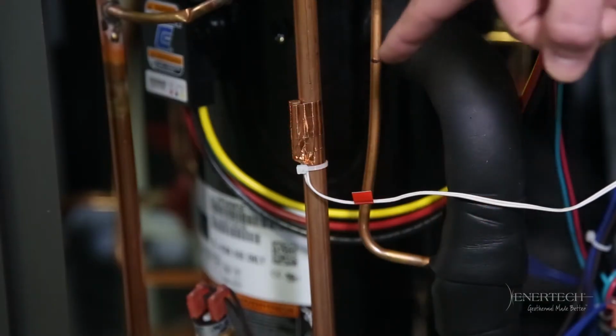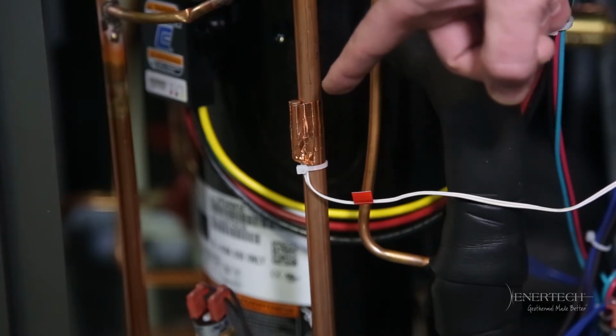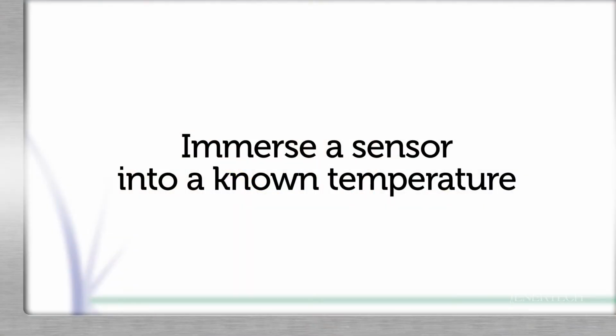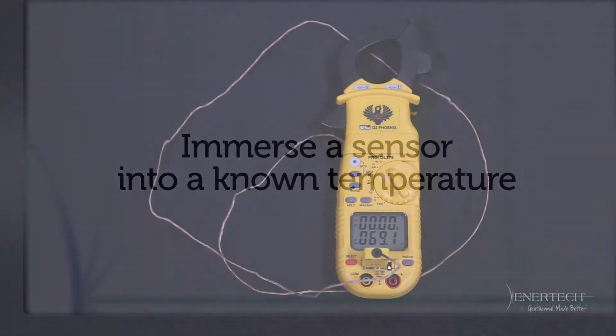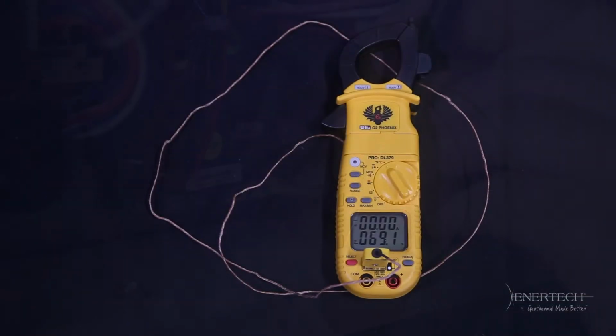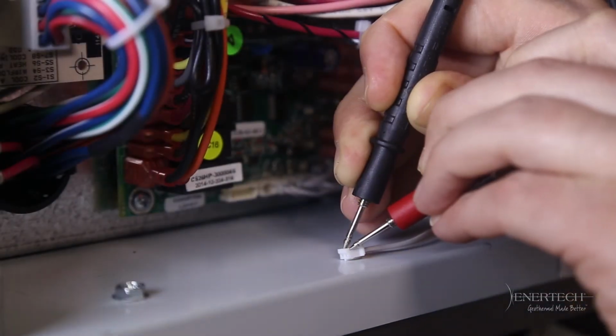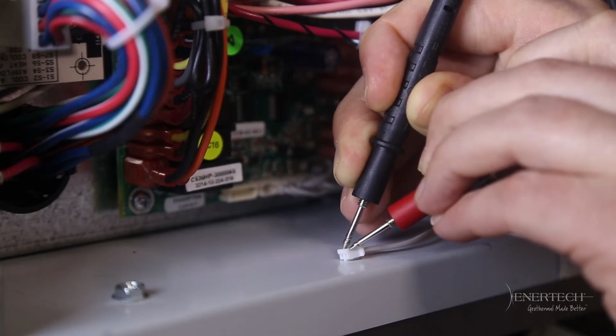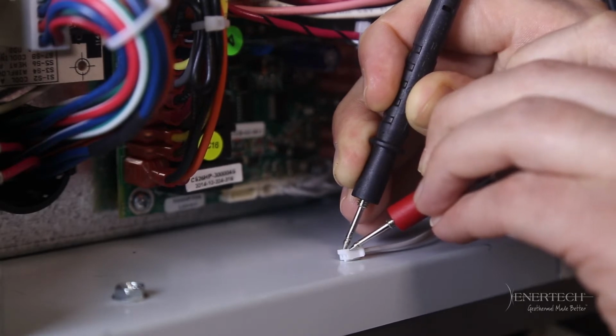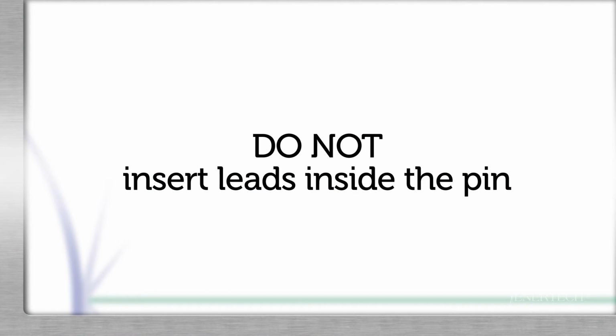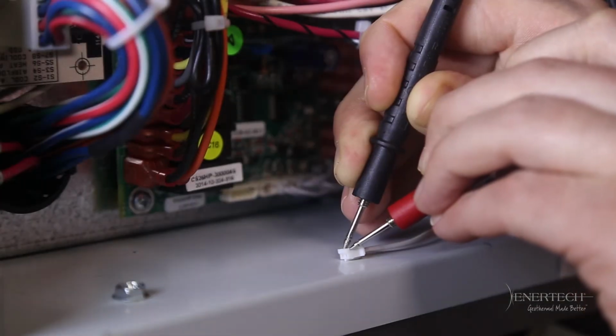To test a sensor, you must immerse the sensor into a known temperature. For example, immerse the sensor in a 32-degree ice bath or a known air temperature. You must use very pointed test leads, fine enough for tiny surfaces, and measure on the outside of the sensor connector. Important, do not insert leads inside the pin. You may ruin the connector. Fine tips are available for most meters as an accessory.